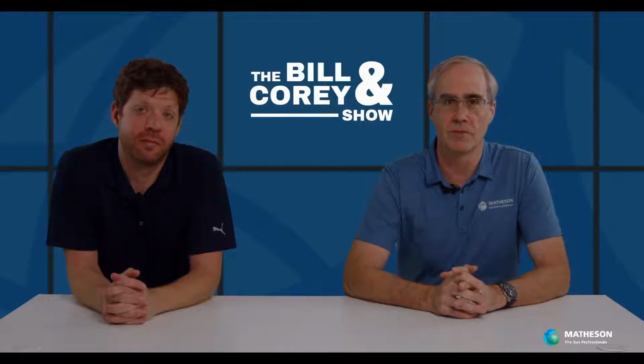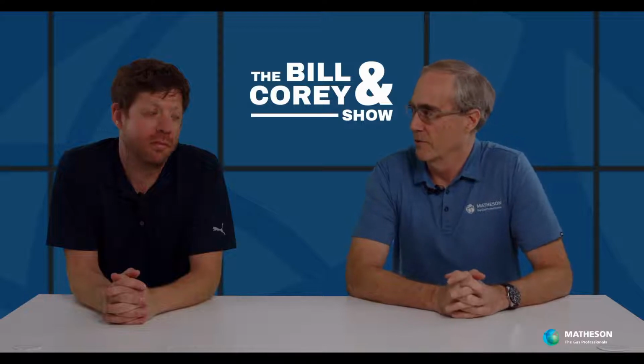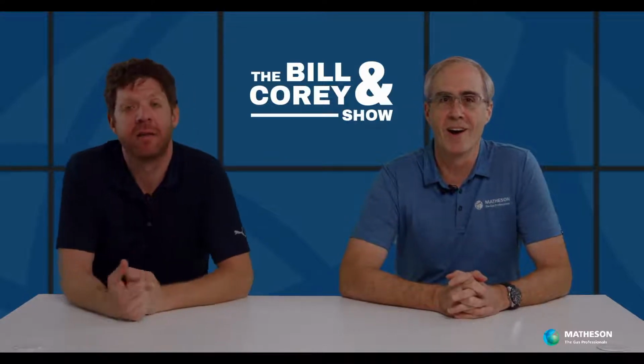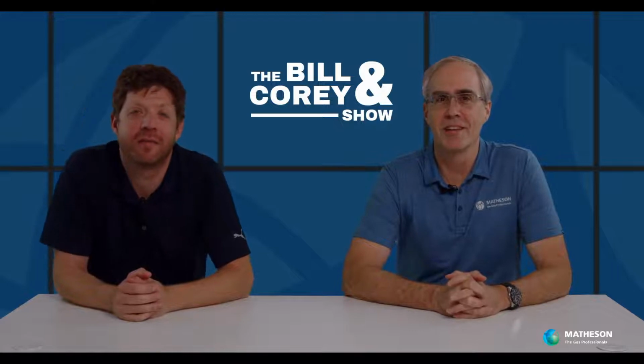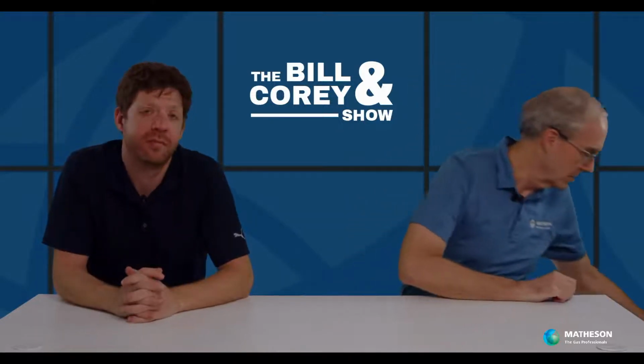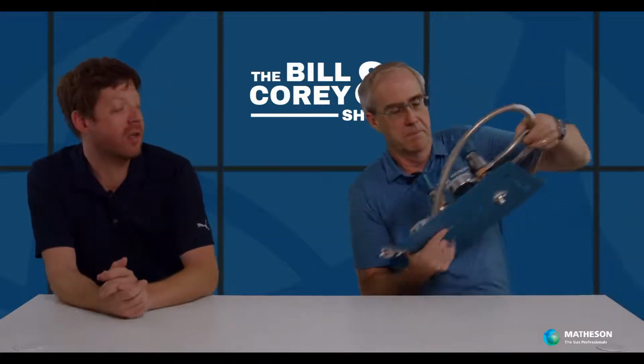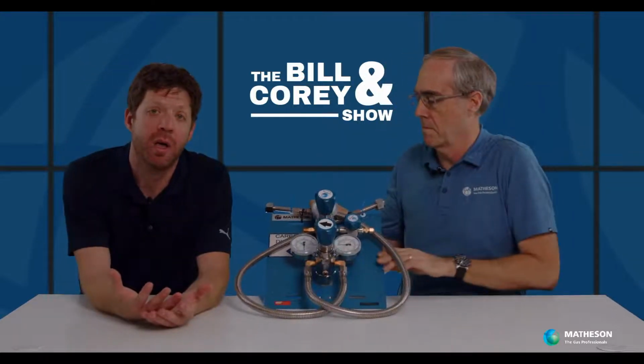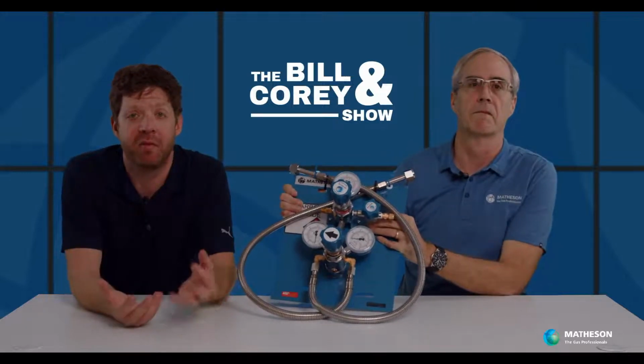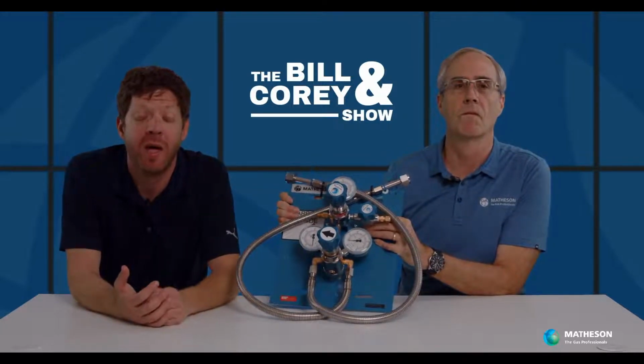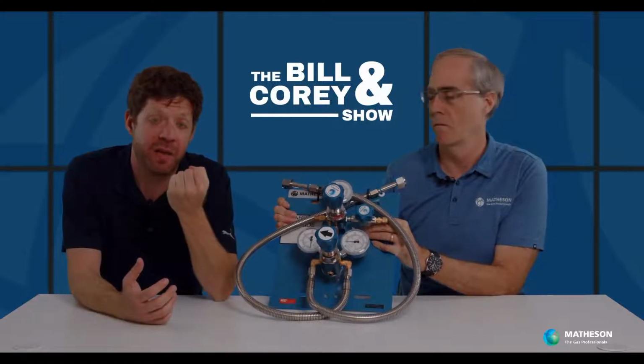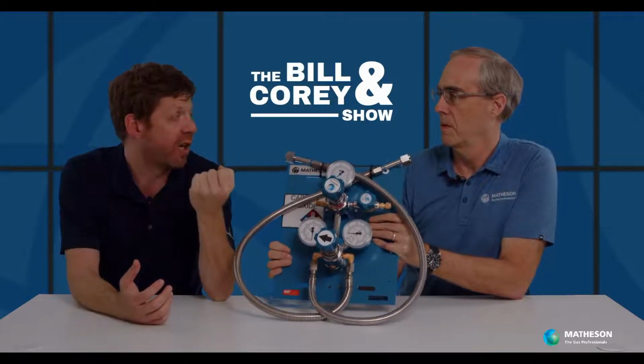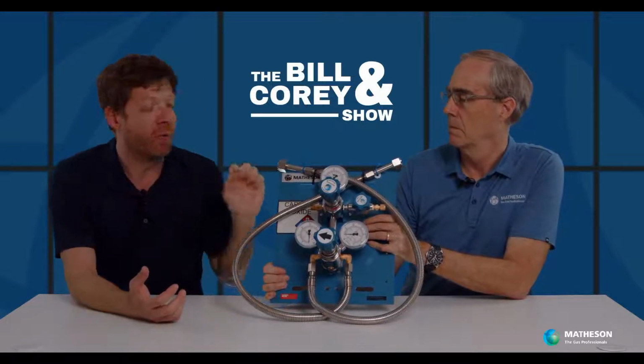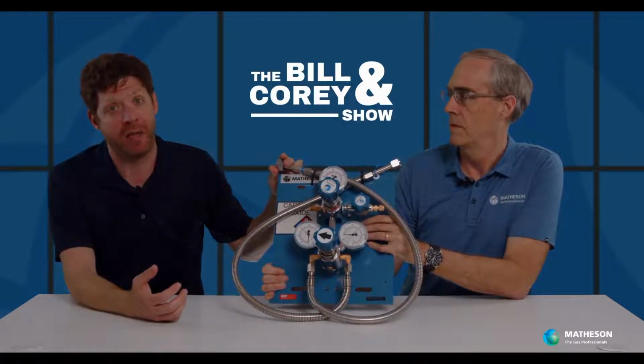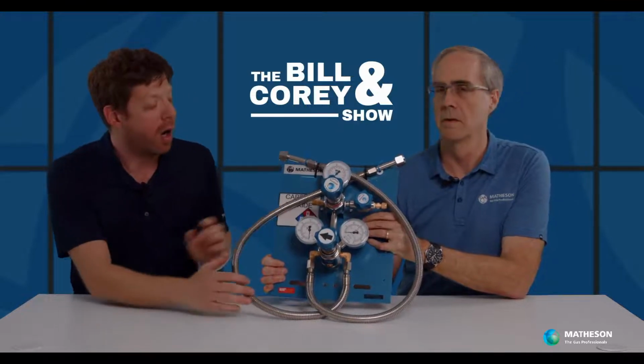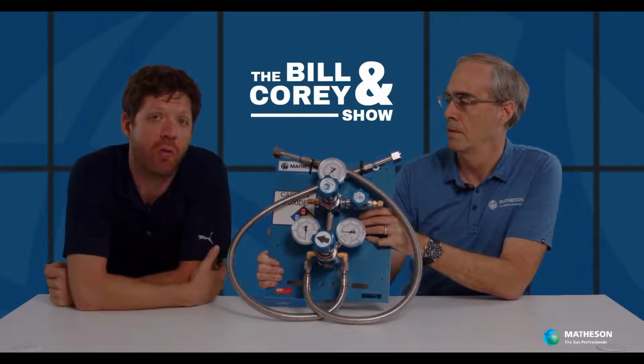Okay. So the next question is for Corey, and I get to hold the switchover this week. Are your switchovers okay to use with dewars, gas use, liquid dewars? Even the question talks about gas use. A dewar is a cryogenic container of liquefied gases, such as nitrogen, argon, oxygen, or CO2. It has a gas connection, and it also has a liquid connection. When we send it to you, it will only have connections that connect to the gas side. So in short, yes, our switchovers will definitely work with dewars.